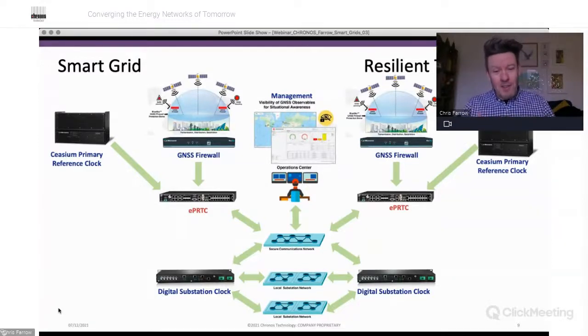On this slide there's no demarcation between telecom and protection. We're looking at timing particularly, and within the substation, at the bottom of the slide, the digital substation clocks are using Ethernet networks. These clocks can be traceable to UTC. I know lots of measurement and monitoring applications don't need absolute time within the substation - they only need a time base so they can make relative measurements. But great efficiencies can be achieved if the whole network uses the same time reference.